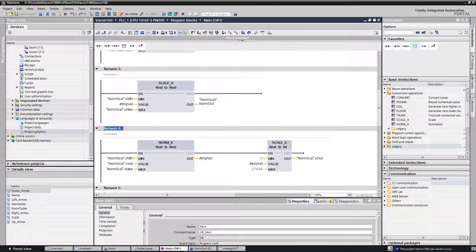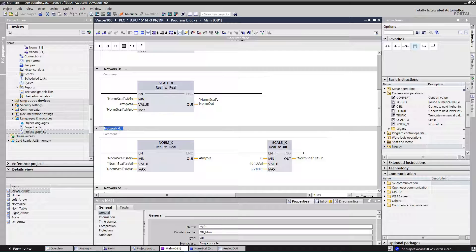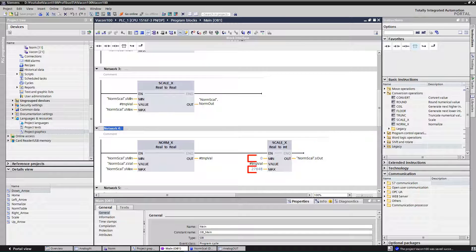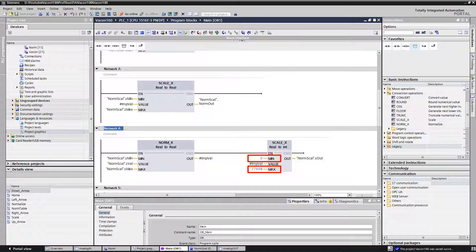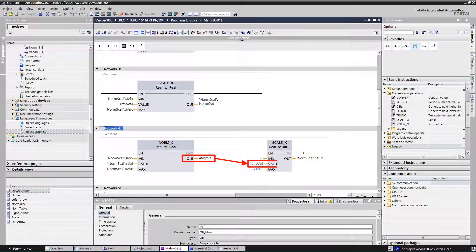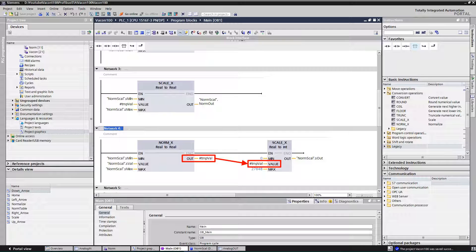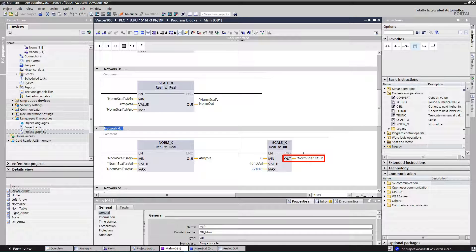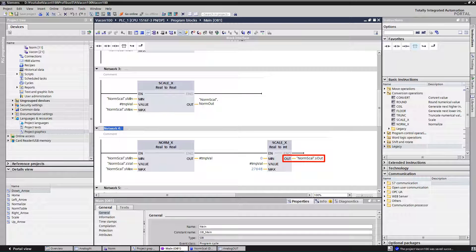Now we need to scale the NORM_X result to the range of 0 to 27,648. Drag and drop SCALE_X instruction to your network. Assign 0 to input min and 27,648 to input max. Assign result of the NORM_X instruction to the input named value. The result of this instruction will be value within 0 to 27,648.